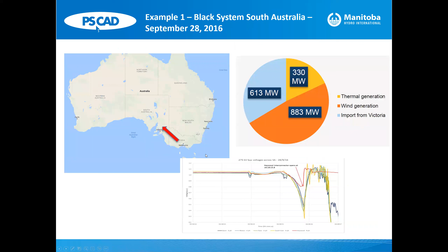We saw here part of the Australian system, where there are lots of power electronics connected in a meshed form. There were some control interactions, low frequency voltage oscillations, an interaction between multiple devices in this region. This 8 hertz phenomenon arose, and it was only when we were able to model a big portion of the system using vendor level models that we could capture and replicate the 8 hertz seen in real life. 8 hertz is a problem for things such as flicker, and this has to be addressed.